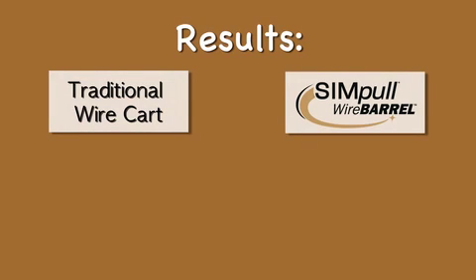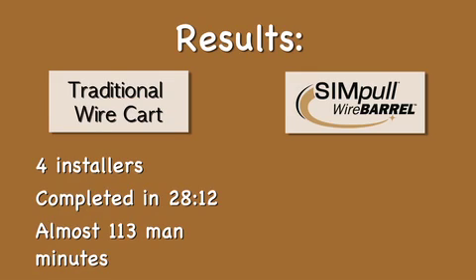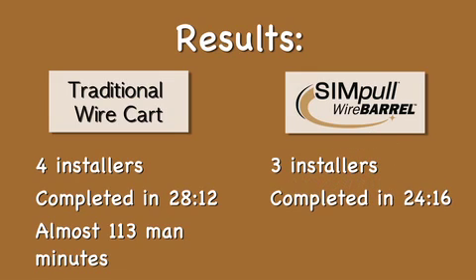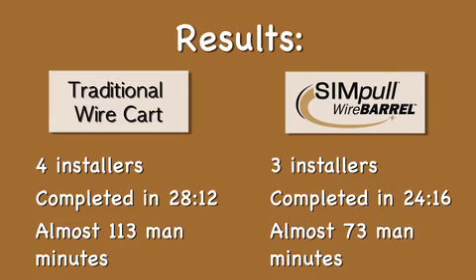The results of the second comparison show that four installers using the traditional wire cart method completed their pull in 28 minutes 12 seconds, a total of almost 113 man minutes. The three installers using the SIMpull WireBARREL system completed their pulls in 24 minutes 16 seconds, or an equivalency of almost 73 total man minutes, resulting in a total manpower savings of approximately 36%.